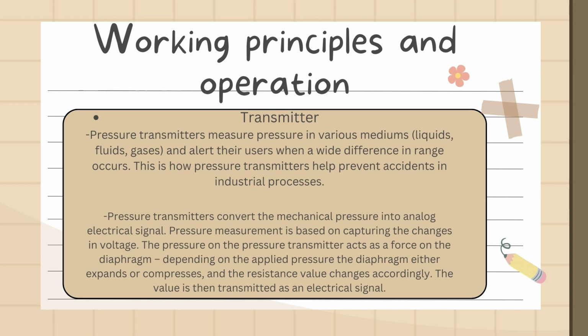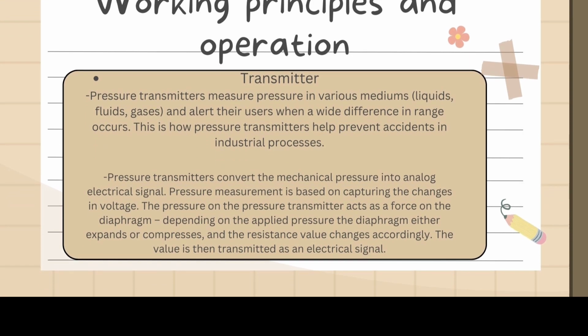transmitters is that they convert the mechanical pressure into an analog electrical signal. And this pressure measurement is based on capturing the changes in voltage. The pressure on the pressure transmitter acts as a force on the diaphragm. Depending on the applied pressure, the diaphragm either expands or compresses, and the resistance value changes accordingly. The value is then transmitted as an electrical signal.